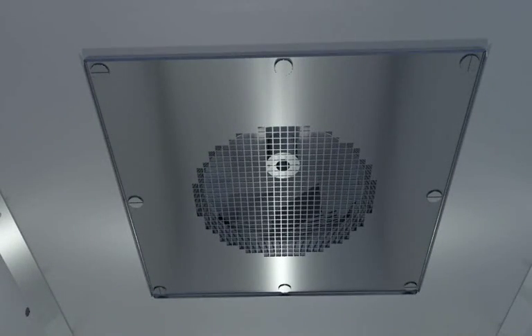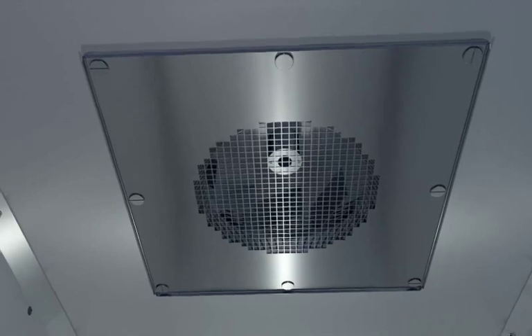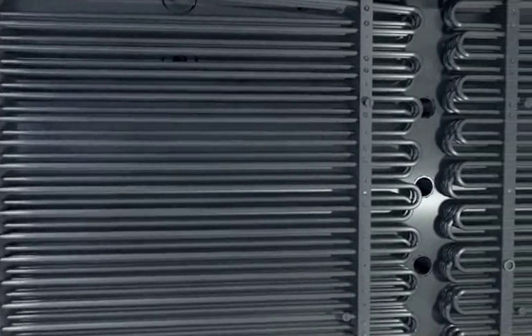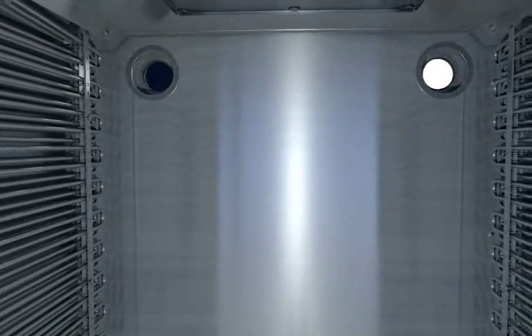A custom-designed stainless steel centrifugal fan with hygienic mechanical seal delivers high airflow rates. A multi-speed fan is available with the GEV TS Turbo, which provides increased process control. Unlike the GEV TS, the GEV TS Turbo includes a slotted liner designed to accommodate various load configurations. The unique slotted liner utilizes lateral airflow, fabricated from sealed, one-piece stainless steel tubing.